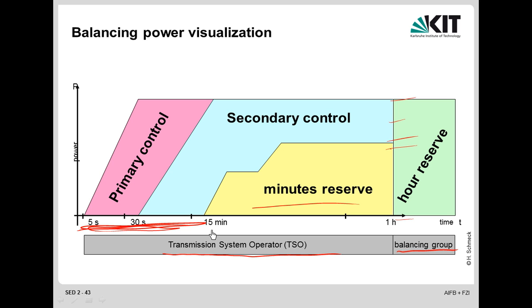And the ingenious part is that in order to start the primary control, you don't need to communicate. It's just looking at the frequency, which is the same at every location. You measure the frequency locally, and you notice a deviation from 50 Hertz. And if you have a contract for providing primary control, your device has to provide primary control power proportional to the deviation of the frequency from this 50 Hertz goal. And so it's a proportional supply of primary control depending on the current frequency. No communication is necessary. Works perfectly.